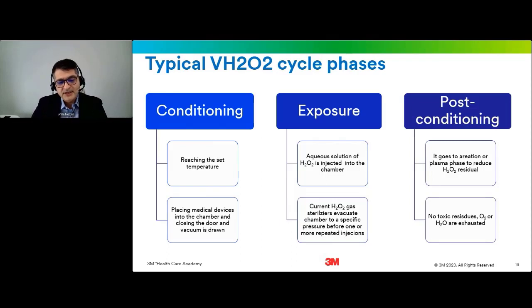Let's have a brief look at hydrogen peroxide sterilization process cycle phases. These are the general phases that typically apply. As I mentioned earlier, different manufacturers with different sterilizers have different components that might vary a bit. So there are typically three cycle phases. The first phase is the conditioning phase.